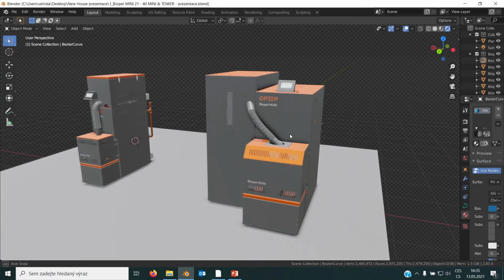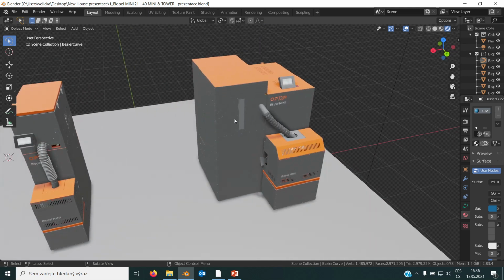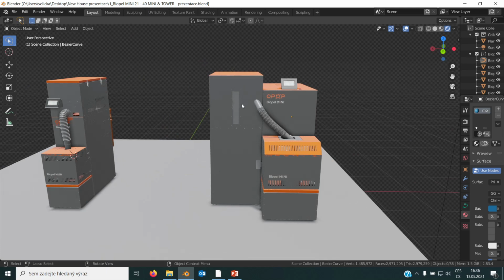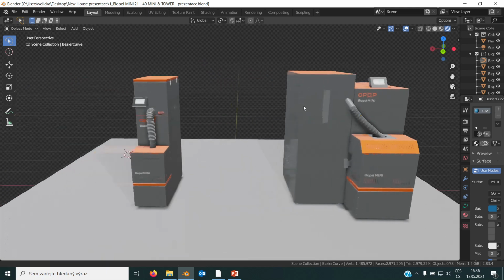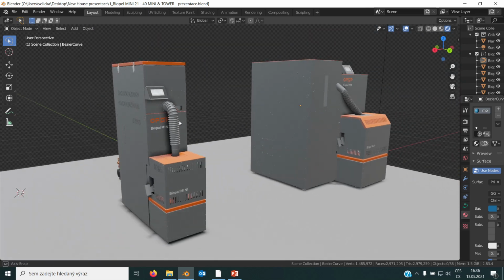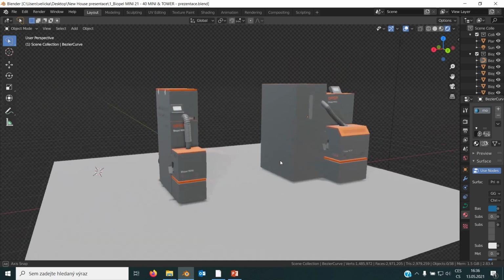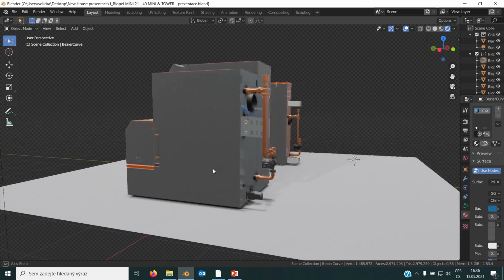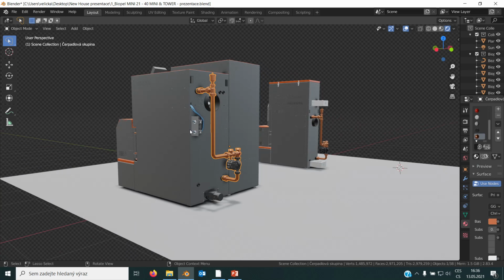As you can see, again, I have two boilers here. On the right side, this is Biopel Mini 20 to 40 kilowatt in compact version with the compact tank. This is the biggest compact tank we can offer you, 225 kilos of pellets. And on the left side, we have Biopel Mini Tower, in this case 11 and 15 kilowatt. Both boilers are with all the accessories, so there is a pump group, there is also heat exchanger and compressor cleaning, and there is of course also an ash removal system.